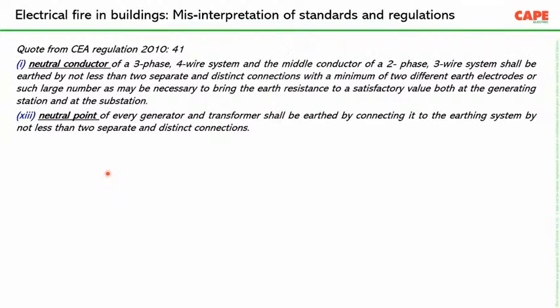Let us just find out what is written in the regulation. Regulation number 41, sub-clause number 1 talks about a neutral conductor. This regulation says that the middle conductor of a two-phase three-wire system shall be earthed by not less than 2 separate and distinct connections with a minimum of 2 different earth electrodes. Yes, of course, the regulation says you should connect it by 2 separate and distinct connections to 2 separate earth electrodes. But what? You should read here, neutral conductor. It is not the neutral terminal of a transformer. It is for a neutral conductor.